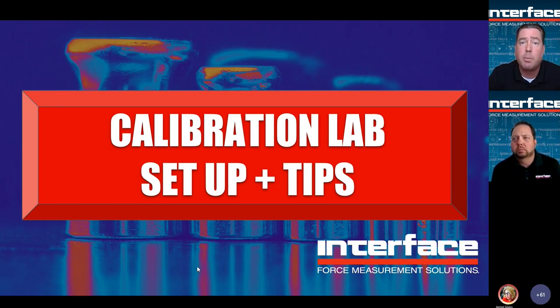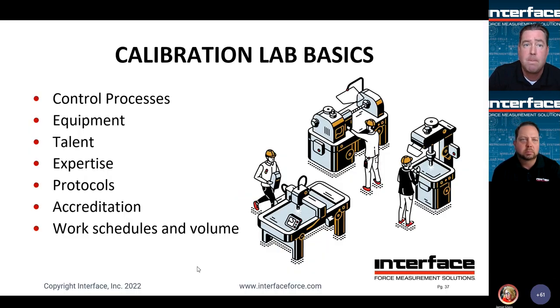All right, so we'll talk about some calibration lab setup and just general tips. As with any production type environment, you will want to make sure that you have very controlled processes that are defined and recorded. That way you have technicians that are not free for interpretation. Equipment is another very important consideration, making sure you have suitable load frames or methods of force and torque application to provide an uncertainty level that's consistent for each calibration.